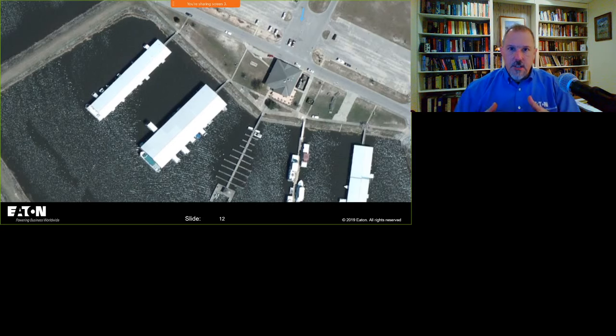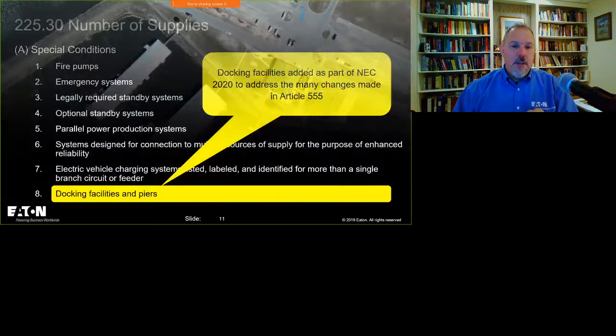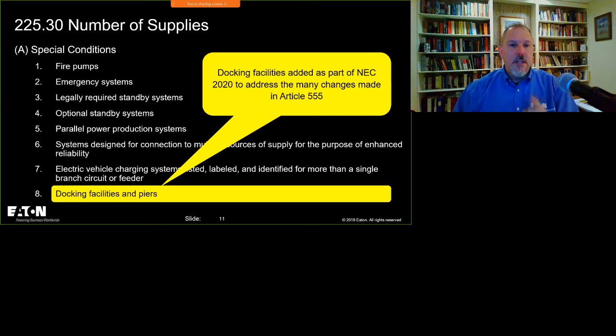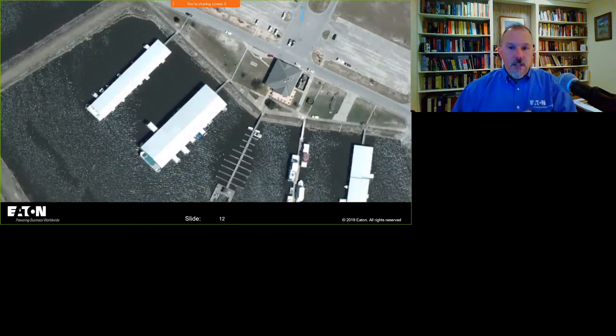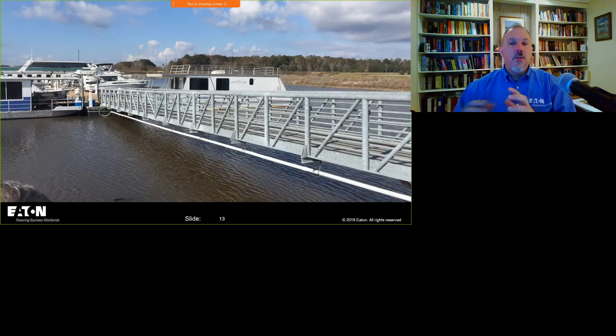And with the changes in ground fault protection of equipment, there was a desire to bring multiple feeders out to that pier, because they know they have to have ground fault protection of equipment on those feeders going out to the pier, but they wanted to separate their loads to avoid the accumulation of leakage currents. Well, in doing that, they can't, because that's a structure. So with this change, by specifically putting that language to permit docking facilities and piers in 225.30(A), these structures are now permitted to have multiple feeders going out to them.